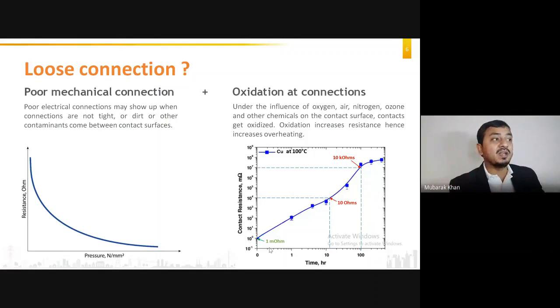Now there can be a loose connection problem because of oxidation at the connections also. What do you mean by oxidation at the connection? Normally we have copper, which is used as a conductor, right? Copper has excellent conductance, very low resistance over the length, so it is having very good conductance. But copper oxide, or cuprous oxide, is not such a good conductor.